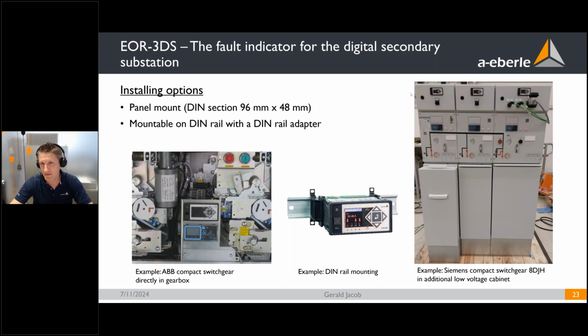On the right side, you can see a compact switchgear station from Siemens, also used in that kind of manner at the Netze BW project or standard. As you can see, there's also a spare place which could be used by the device, but Netze BW wanted an additional low voltage compartment on top with doors in each cable field and in the transformer field, where a local remote switch and the devices can be inserted, along with an internal switch mounted in here.